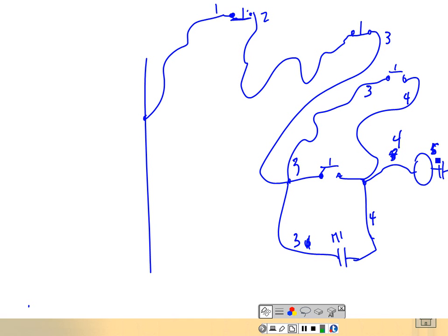You're down here doing something, I got to start this thing back up, and you walk all the way back through here, start it, and you turn around and do what? Walk all the way back. So multiple start-stop stations are very, very common. We're only showing 2, but it could be 3, 4, 5, 6, 7, but all your stops, you would hook in series. Yeah, series.